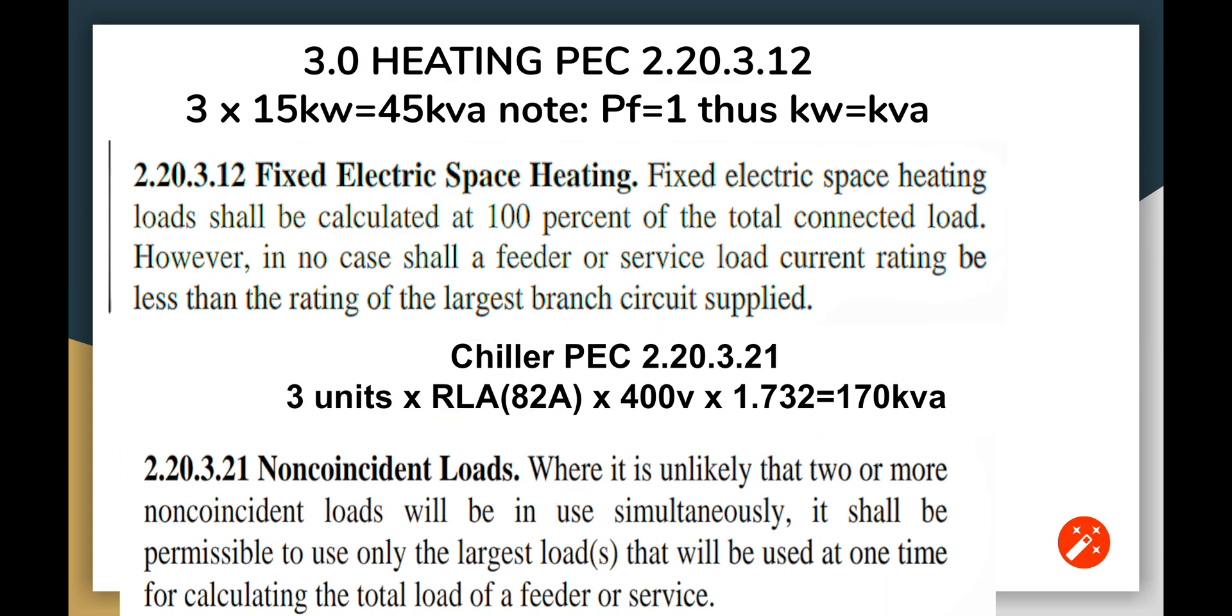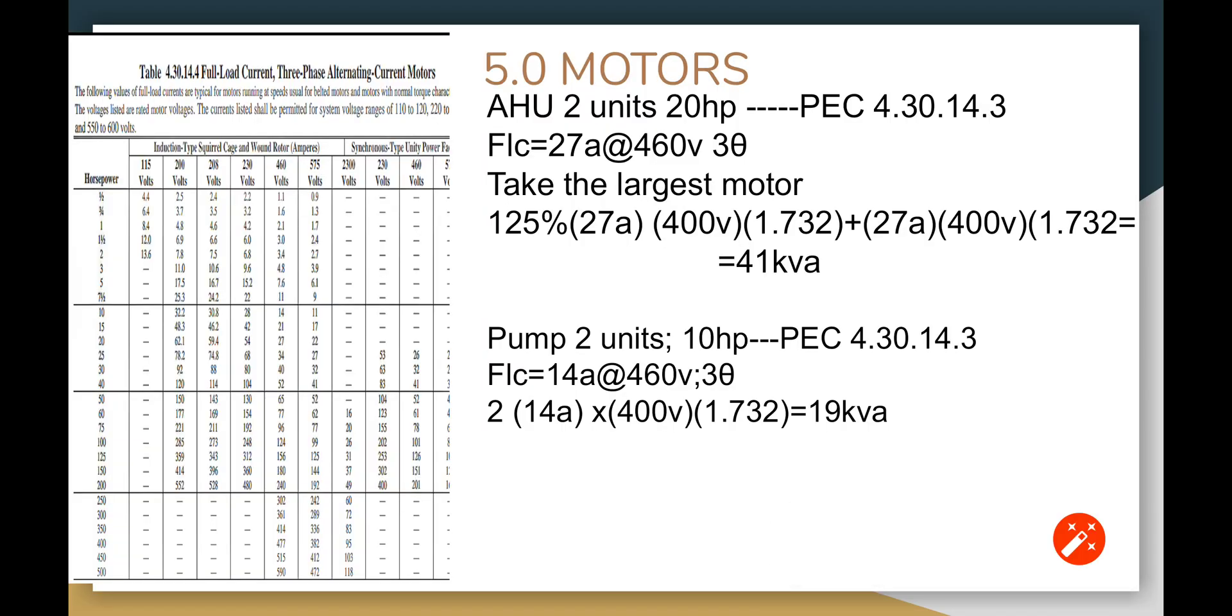We have four motors. We have four units of 20 HP, the FLC is 27 based on PEC 4.30.14.3. The largest of the motor, we have four motors here, the largest one plus 25 percent gives us 41 kVA. So you don't need to add another 25 percent for the pump because it's already counted here in this calculation. For the pumps, two pumps, these are not non-coincidental loads, so they are all used in our calculation for motors.